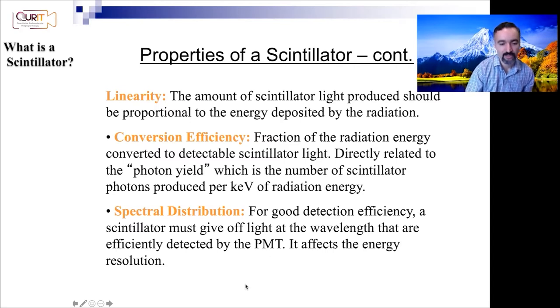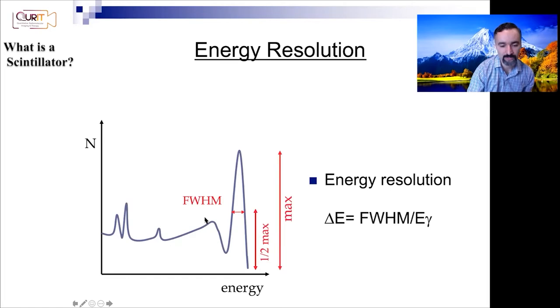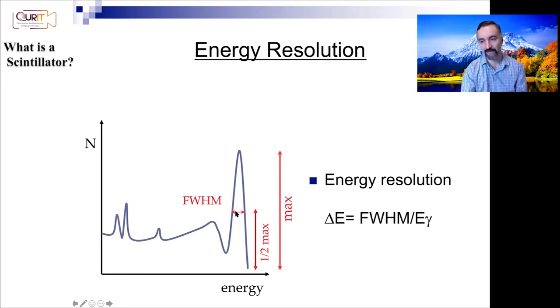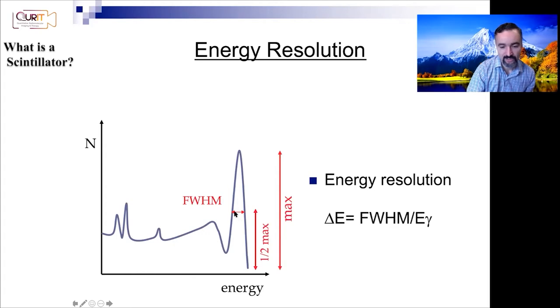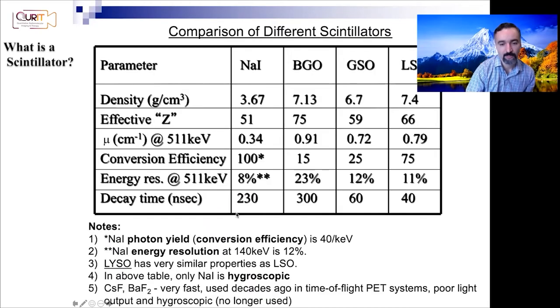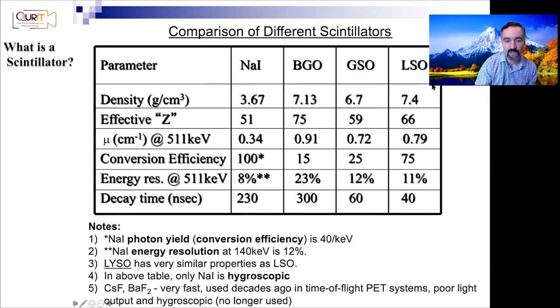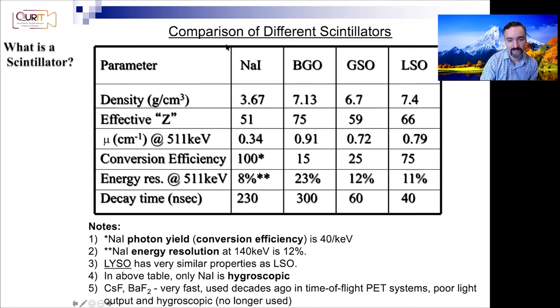Looking at energy resolution: imagine this is 140 keV for technetium. Ideally you want the energy resolution to be very good — a very small full width at half maximum (FWHM), which can also be expressed as a percentage. We'll talk about this more, but let's look at some examples of different scintillators.